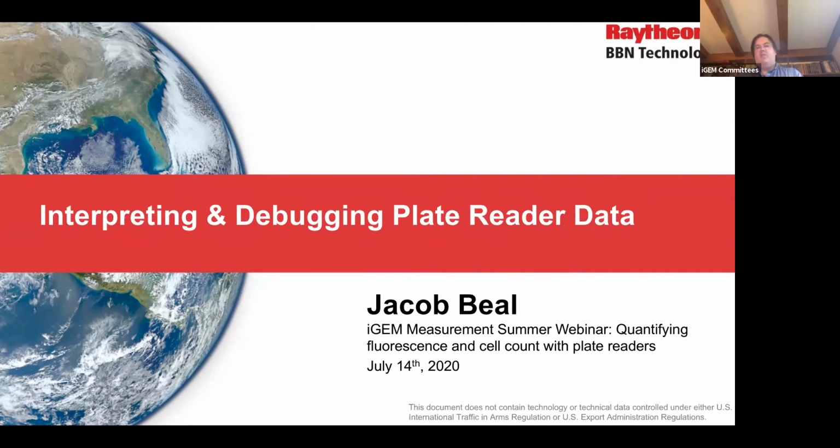And we strongly recommend that you use the numbers that are there if you can, because that way your numbers will be directly comparable to other people who measure using those same numbers. If you excite at 488, then you can put an emission filter at 530/30, and you can compare directly to anyone else who did 488, 530/30.